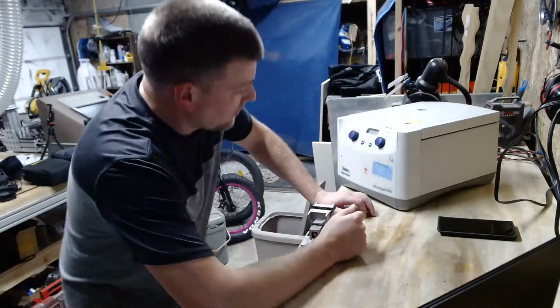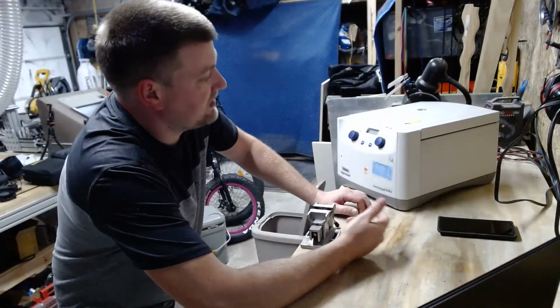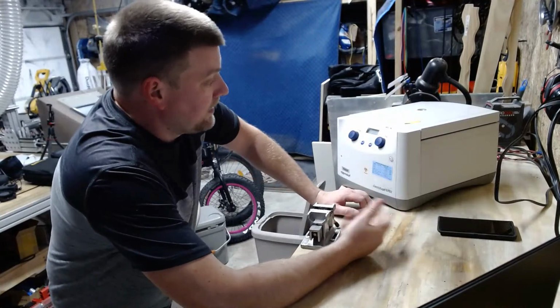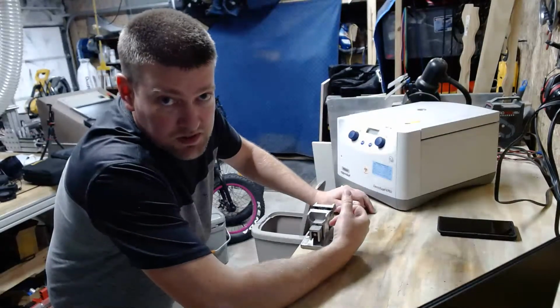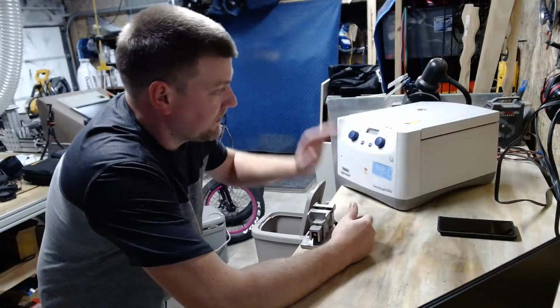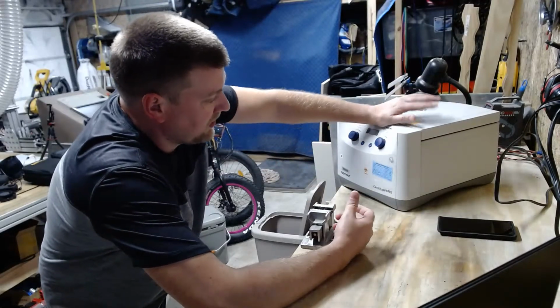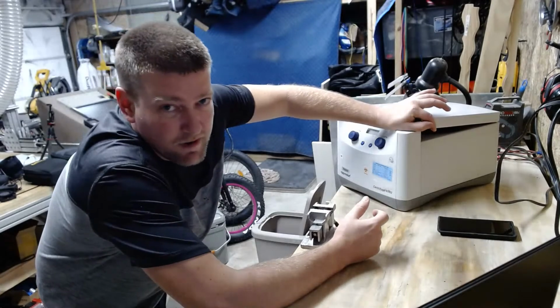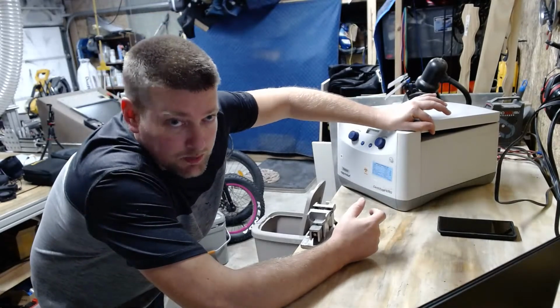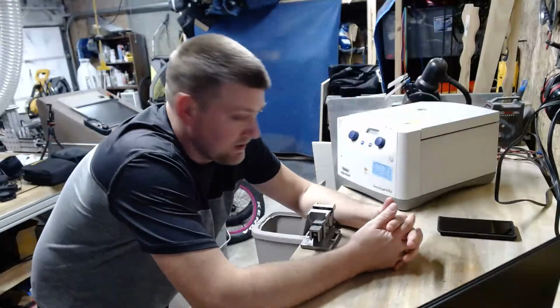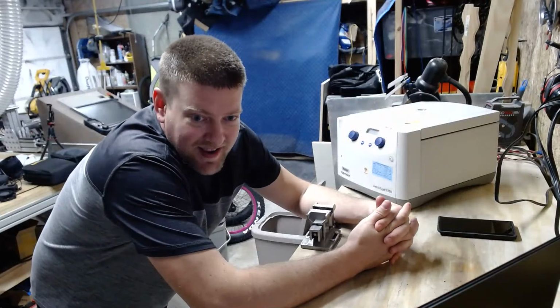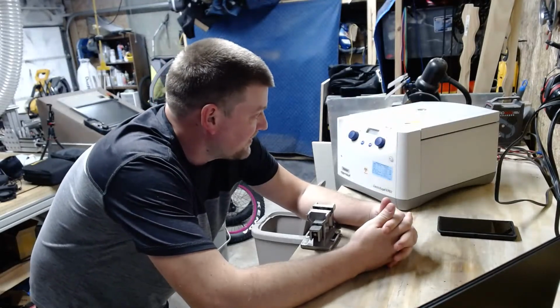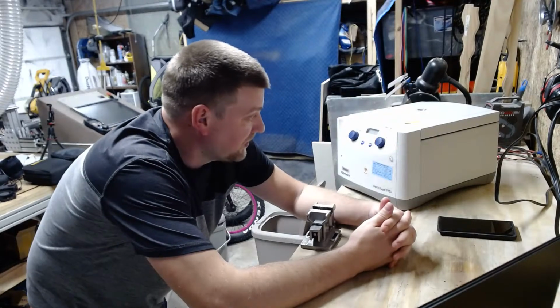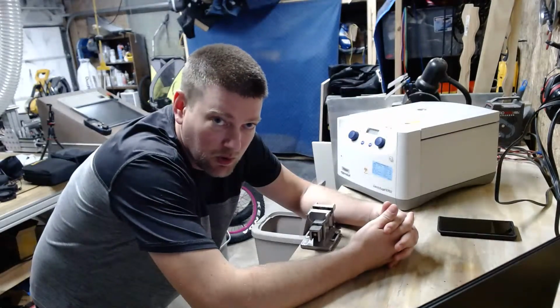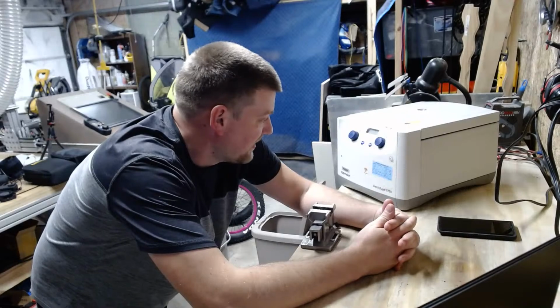So normally what I would do in this case is pull out the back and check the fuses, maybe something like that. These guys, because of the motor - since it's a three-phase motor, it normally has motor protection circuitry. And if it's got motor protection circuitry, that means it probably will not pop those fuses on the back. That's more for like a short circuit or something like that.